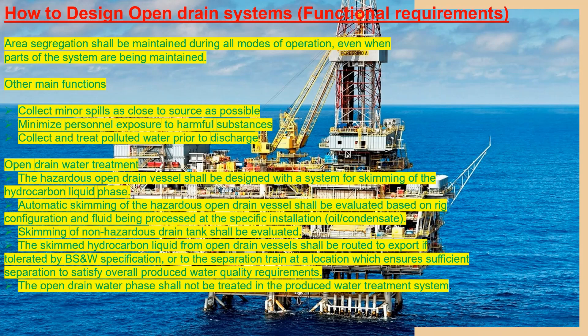Skimming of hazardous drain tanks shall be evaluated. The skimmed hydrocarbon liquids from the open drain vessel shall be routed to export if tolerated by BS&W specification, or to the separation train at a location which ensures sufficient separation to satisfy the overall produced water quality required. The open drain water phase shall not be treated in the produced water treatment system.